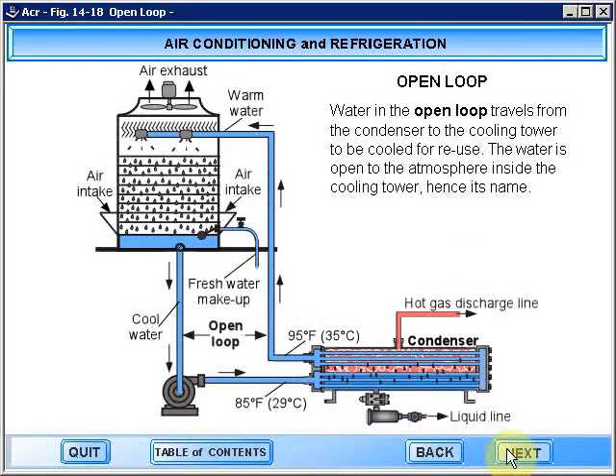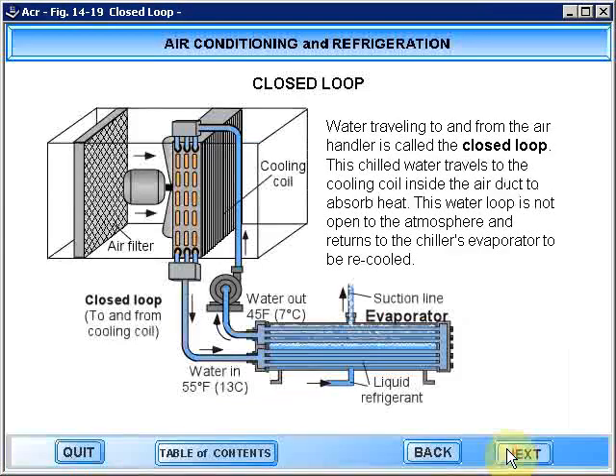Water in the open loop travels from the condenser to the cooling tower to be cooled for reuse. The water is open to the atmosphere inside the cooling tower, hence its name. Water traveling to and from the air handler is called the closed loop. This chilled water travels to the cooling coil inside the air duct to absorb heat. This water loop is not open to the atmosphere and returns to the chiller evaporator to be recooled.